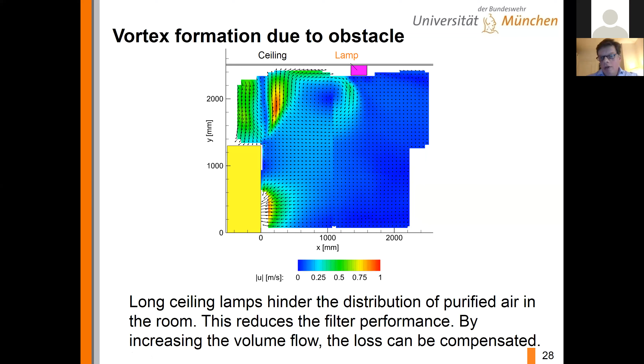So when you install these kind of devices, look for an area where the ceiling is free from obstacles. And then you can make sure that the performance works quite well, because this is not optimal when you have this kind of recirculating flow in this area over here. But on the other hand, you could see, even if you have these kind of side effects, you can easily compensate that by raising the volume flow slightly, and then it's working again quite well. Okay, that's about the importance of the ceiling. Ceiling must be as clean as possible.